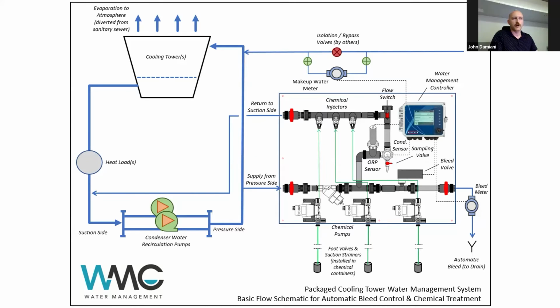Metering is really important. We're metering the water coming in, but you can and should also install a meter on the bleed. There are two reasons for that. Number one, you can control your chemical feed based on either makeup or bleed, and different situations call for different priorities, where one may be advantageous compared to the other.